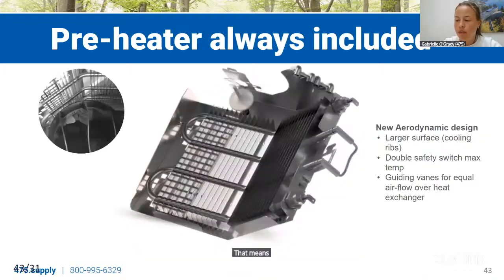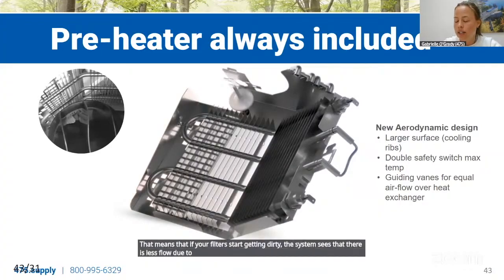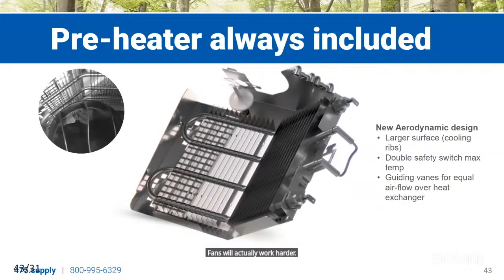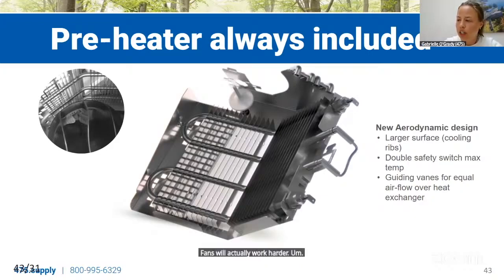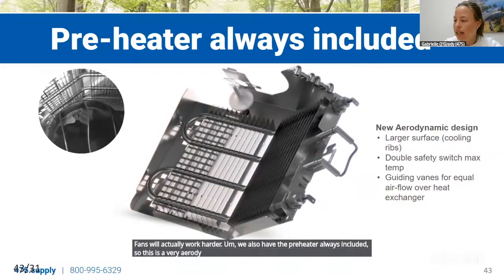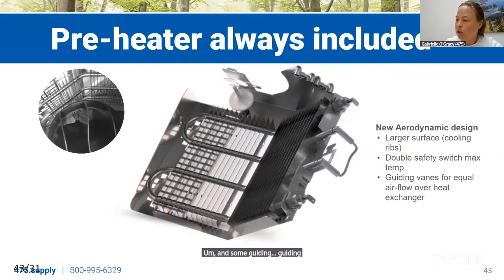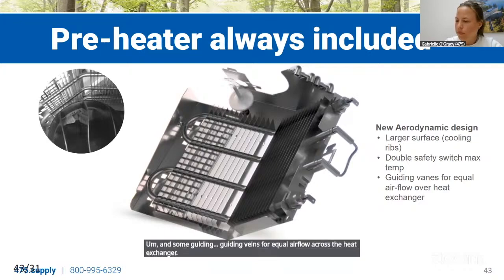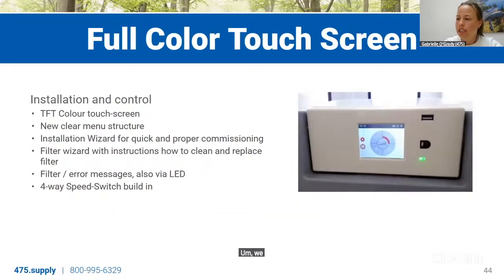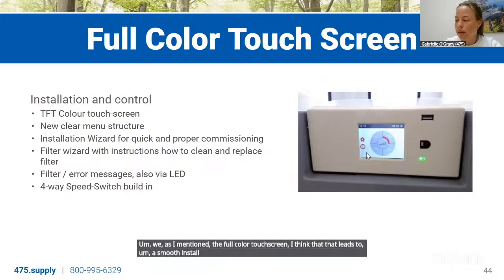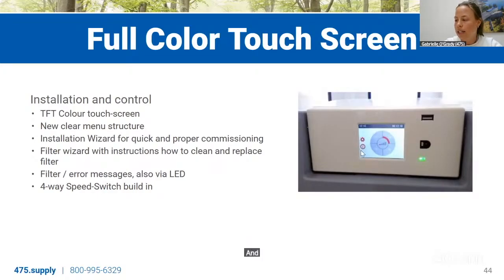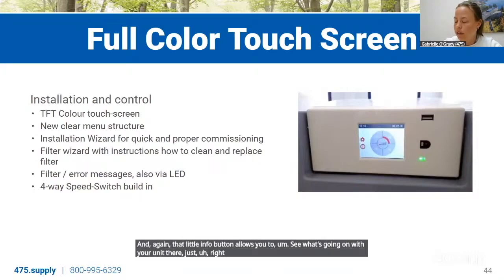That means that if your filters start getting dirty, the system sees that there is less flow due to that, and the fans will actually work harder. We also have the preheater, always included. So this is a very aerodynamic design, leading to very little resistance, and some guiding vanes for equal airflow across the heat exchanger. As I mentioned, the full color touch screen, I think that leads to a smooth install, smooth commissioning setup process. And again, that little info button allows you to see what's going on with your unit, right from the touch screen.